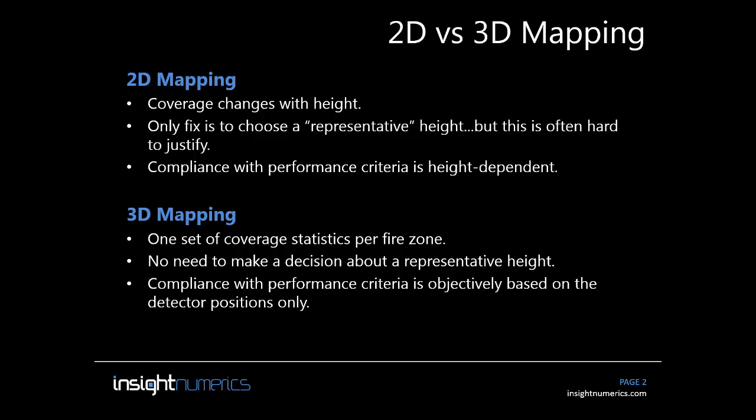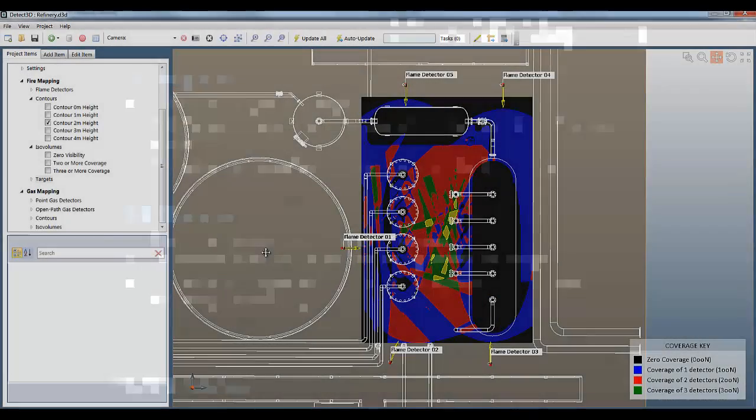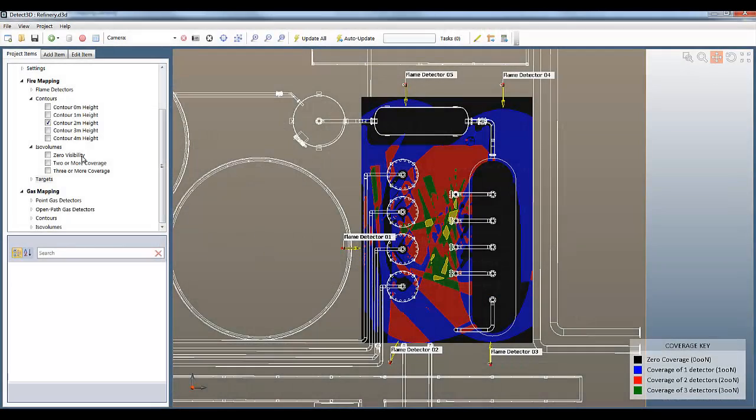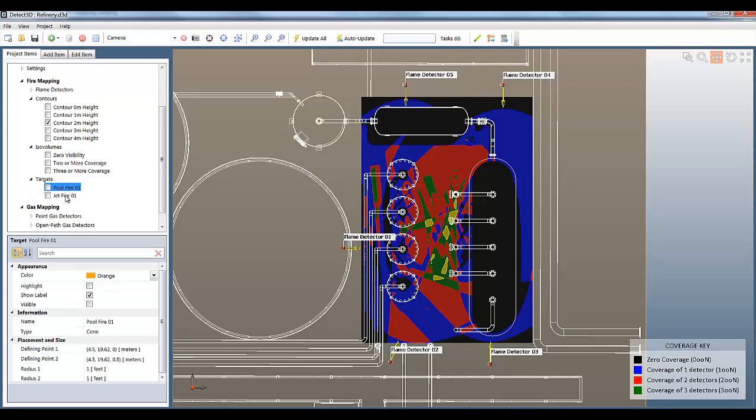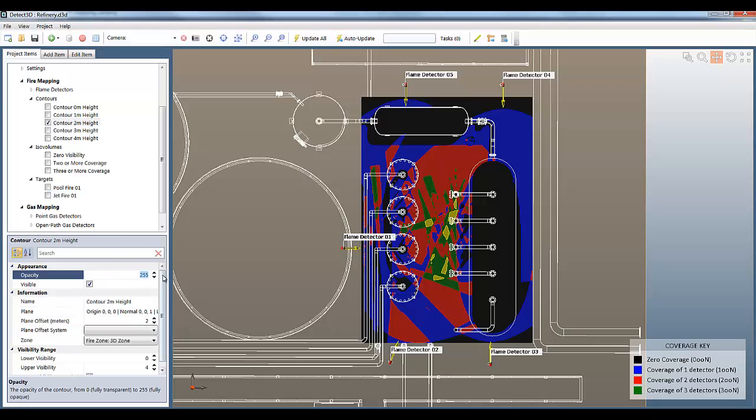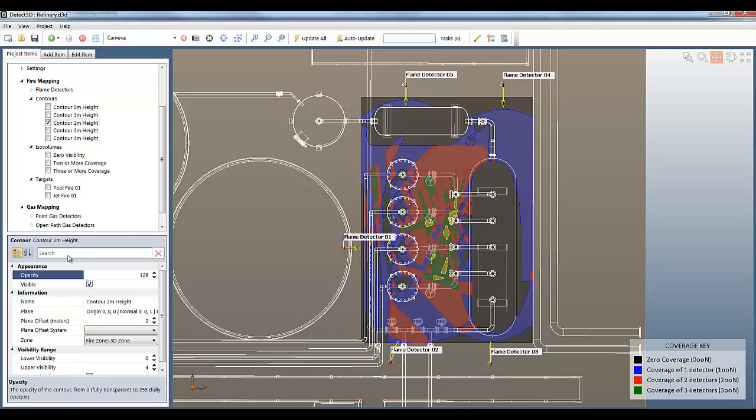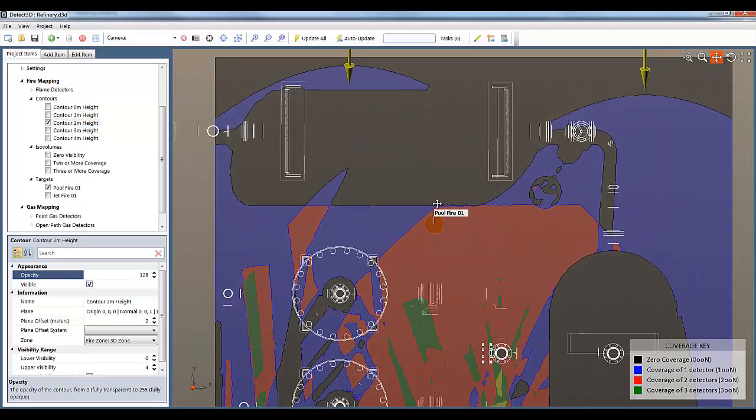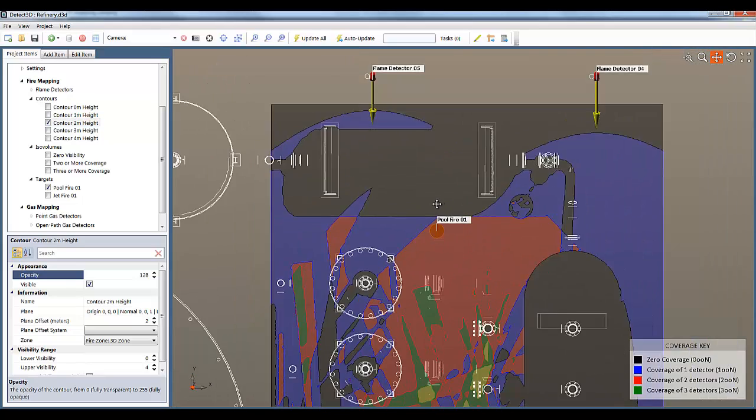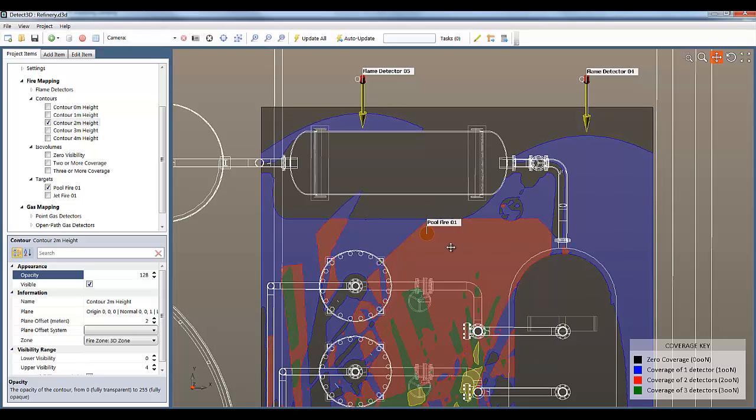I can make the same point a slightly different way using fire targets in Detect3D. Using this technique I can add cylinders and cones in the fire zone to simulate a real fire and determine which detectors can see it. The first fire I'm going to look at is a pool fire. The question is how many detectors is this fire visible to? You can see the fire in orange and it's in a red area indicating coverage by 2 detectors.